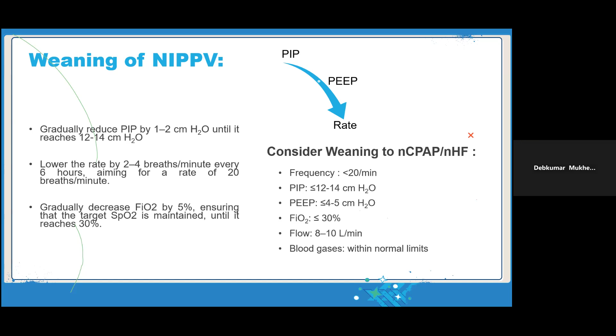One important thing you should remember, when you are using a ventilator where you have to adjust the flow manually, always try to keep the flow as minimum as possible, maybe 5 liters or 6 liters, not 8 to 10 liters. Suppose we have set initially 8 to 10 liters or 12 liters, but after some time we have seen that even with 6 liters the same amount of pressure is delivered. That time we have to reduce the flow.